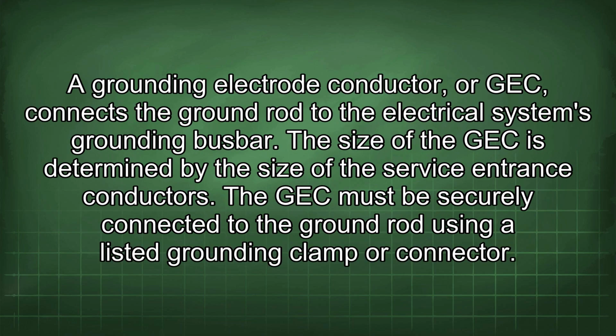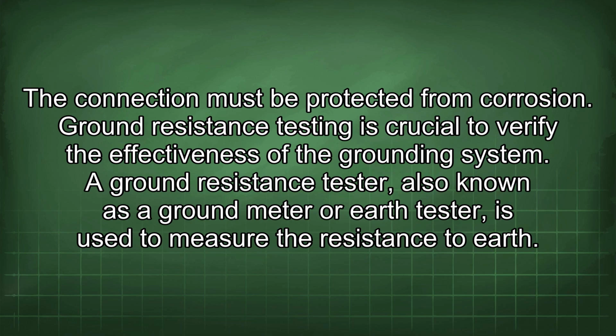A grounding electrode conductor, or GEC, connects the ground rod to the electrical system's grounding busbar. The size of the GEC is determined by the size of the service entrance conductors. The GEC must be securely connected to the ground rod using a listed grounding clamp or connector. The connection must be protected from corrosion.